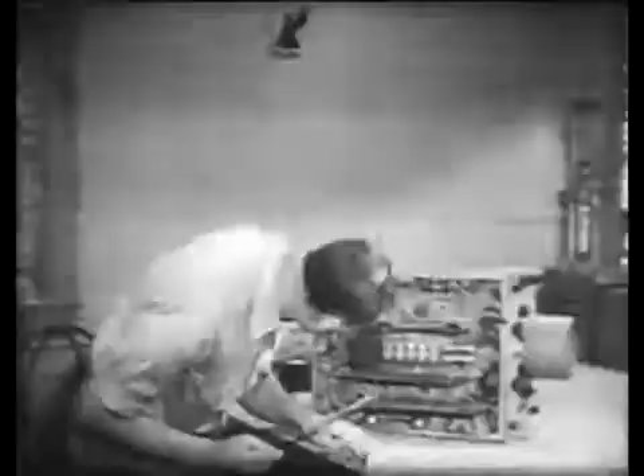When all the large capacitors have been discharged, the circuits should be dead. But a safe worker takes nothing for granted. Always test for the presence of unexpected voltage using a meter known to be functioning. Again, you need the diagram. The meter reads 0. The equipment is dead. It is now safe to proceed with whatever work is required, such as troubleshooting. The resistance checking method is recommended. It's effective and safe.